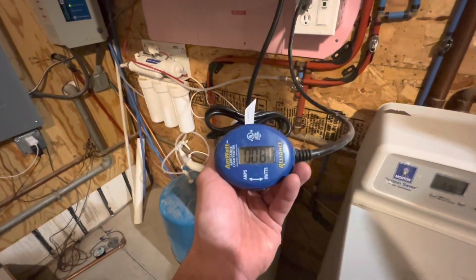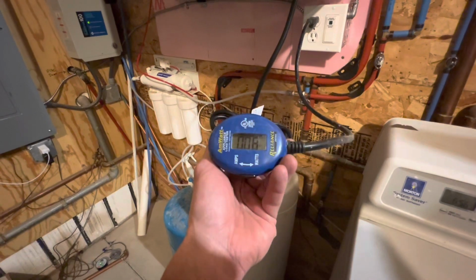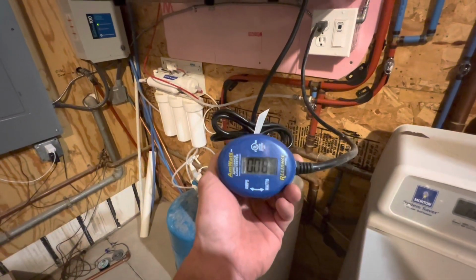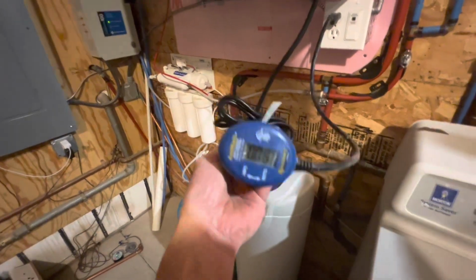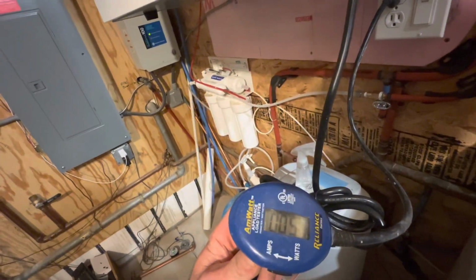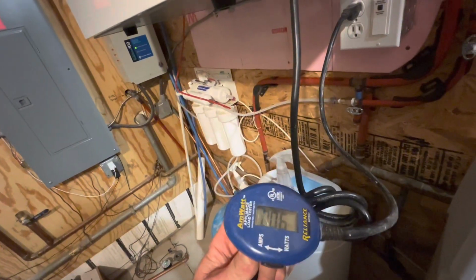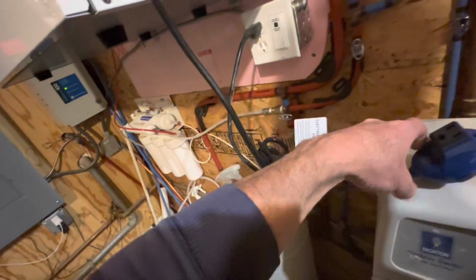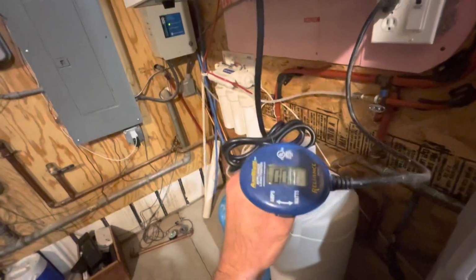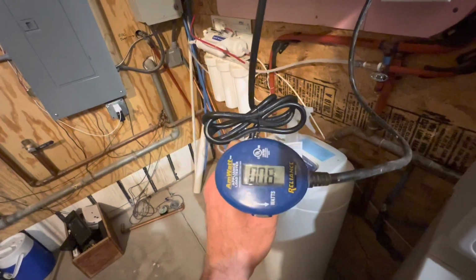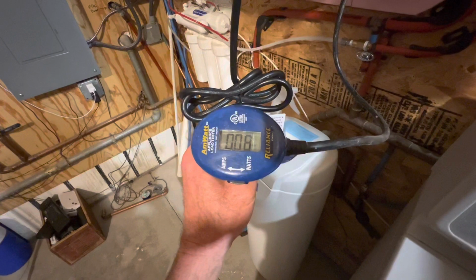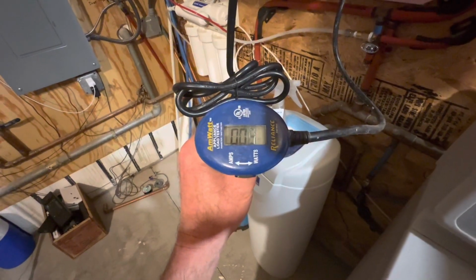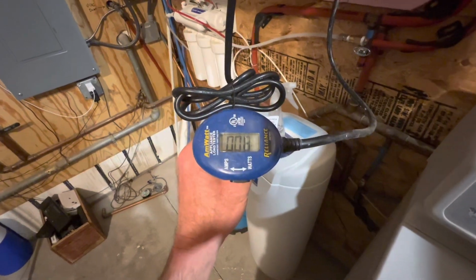So now that the unit's off, you can see that between the green light, the wall controller, and this little watt meter, it's using 8 watts. If I were to unplug the unit itself, I think the watt meter is still going to show 5 to 6 watts. So just with the unit off, between the wall controller and the lights and any other power consumption in the unit, it's about 3 to 4 watts when it's off. And then we saw earlier when it was running, it's about 28 to 30 watts, $2 a day.